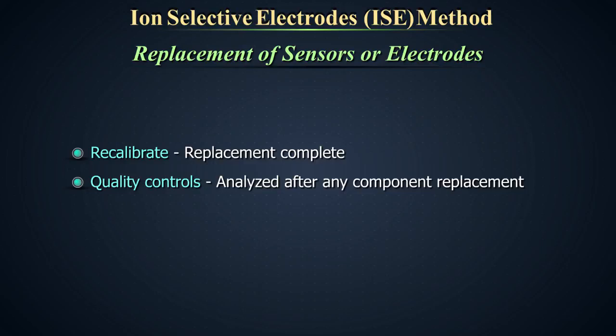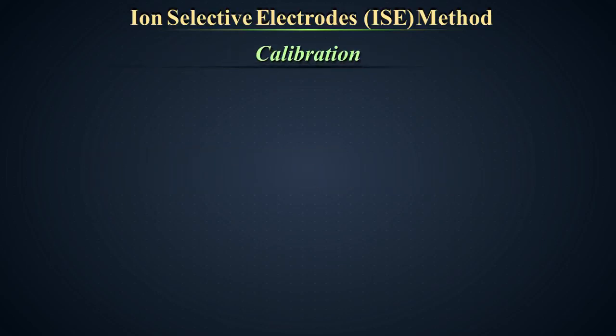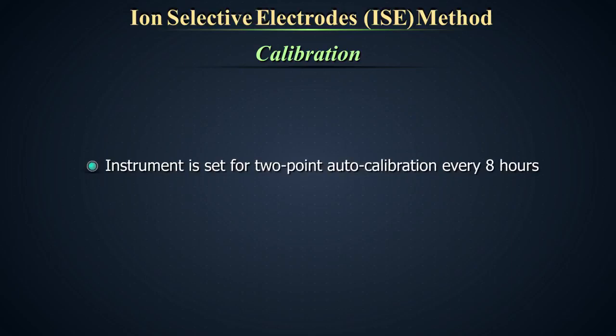Quality controls should be analyzed after any component replacement. Calibration. This instrument is set for 2-point auto-calibration every 8 hours by the manufacturer. It may differ for machines from different manufacturers.